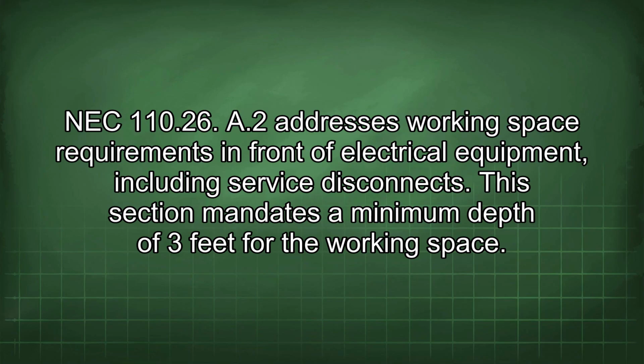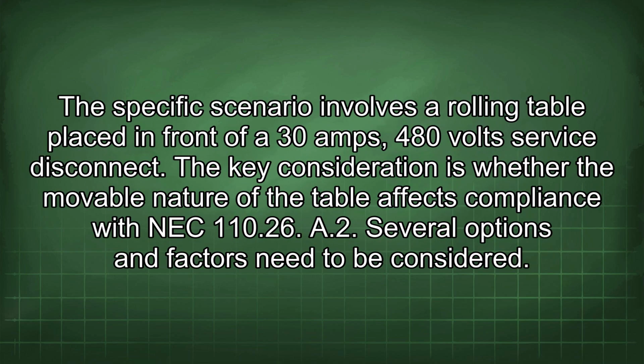NEC 110.26.A2 addresses working space requirements in front of electrical equipment, including service disconnects. This section mandates a minimum depth of 3 feet for the working space. The specific scenario involves a rolling table placed in front of a 30 amp, 480 volt service disconnect. The key consideration is whether the movable nature of the table affects compliance with NEC 110.26.A2. Several options and factors need to be considered.